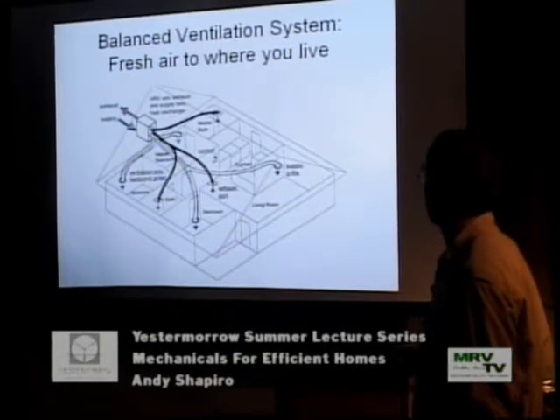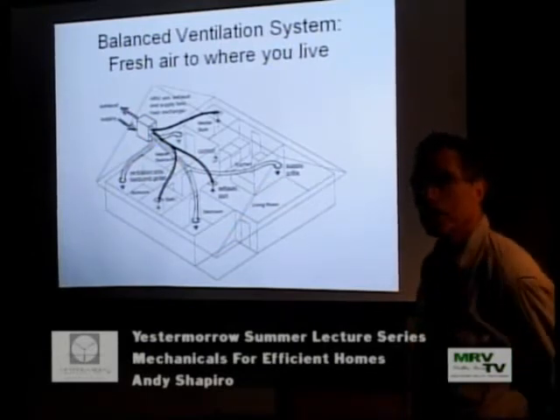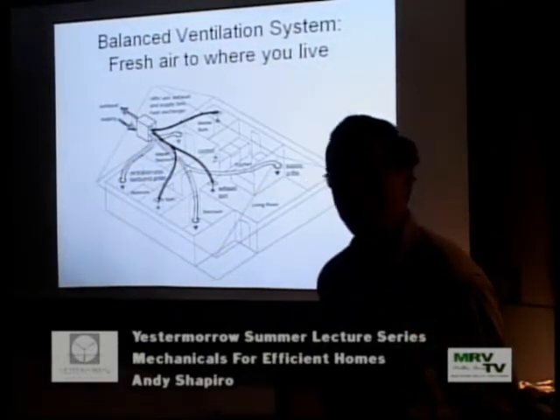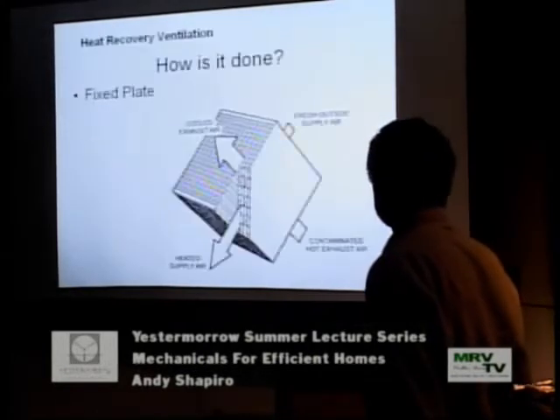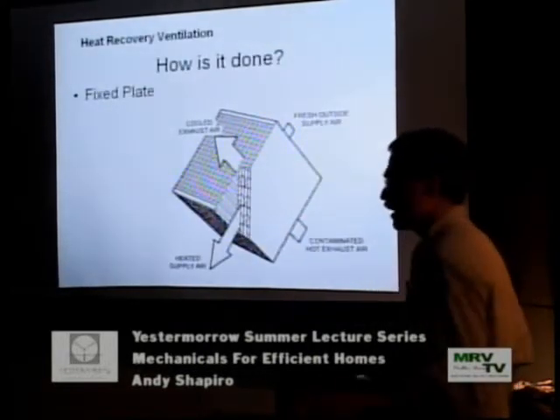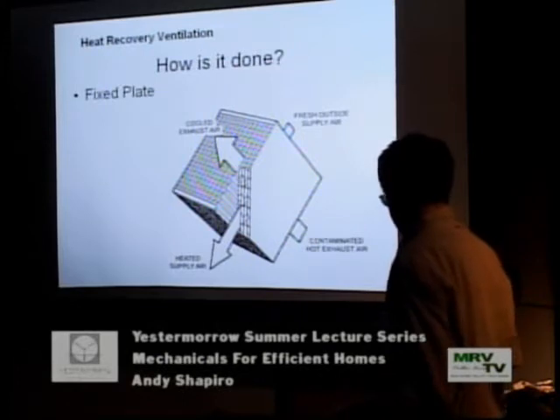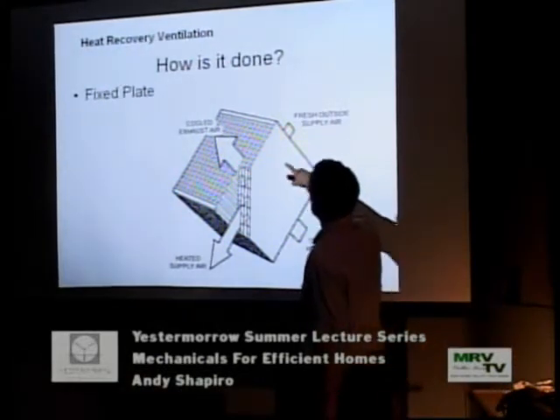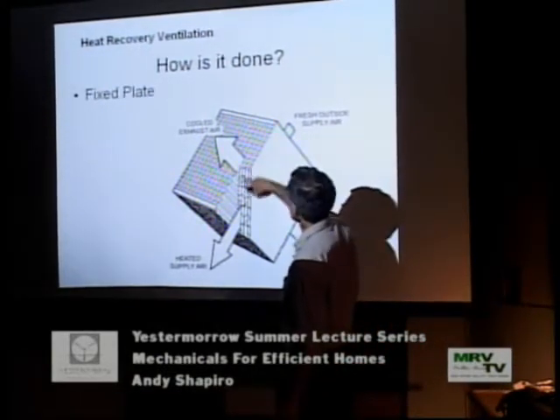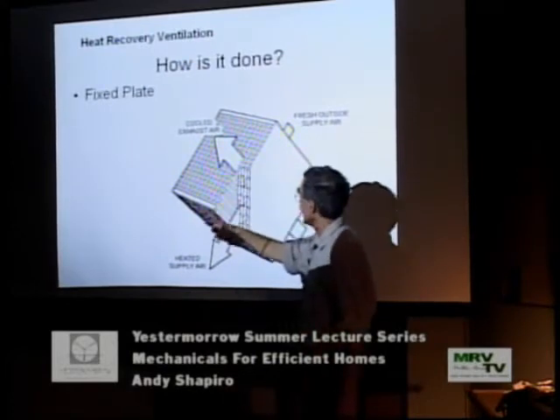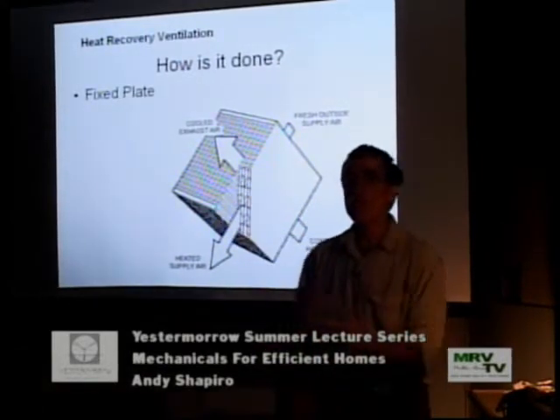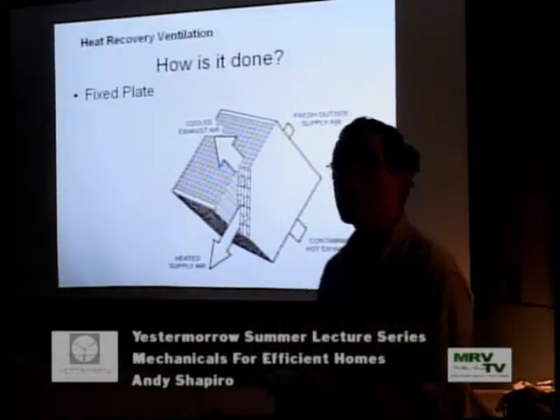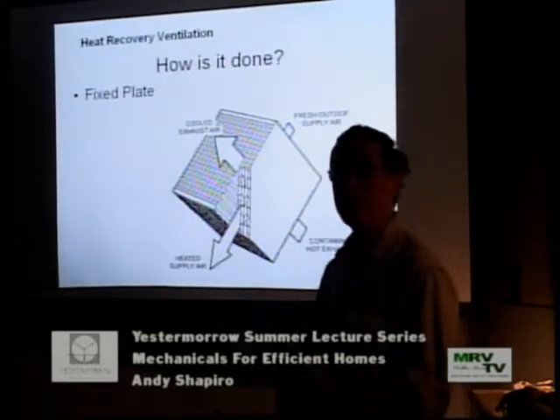What's the difference between an HRV and an ERV? So in an HRV, H is for heat. Everything in here would be made of a rigid plastic usually, sometimes metal, but mostly rigid plastic, so no moisture gets through. You're recovering heat, but you're not recovering any moisture from the outgoing air.